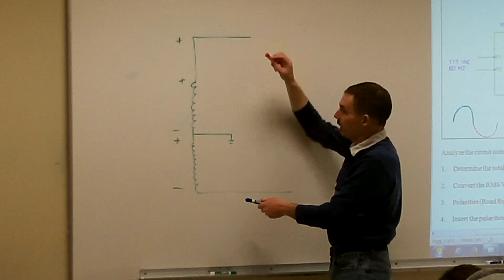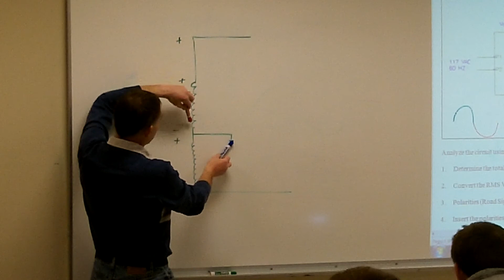If I was referencing it to ground, first, if I go from here to here, I'm going to get my 28.28 volts peak. But if I reference it to ground, going from here, I know half my voltage has to drop across this coil. So what would I measure across this half of the coil? 14.14 volts peak, and the other half would have to drop across here.